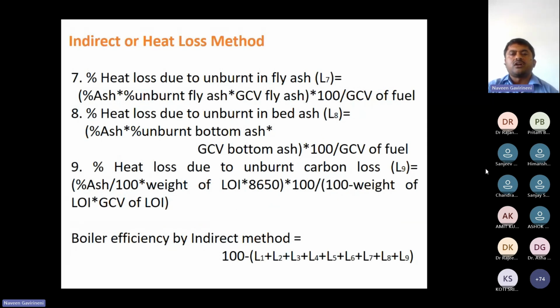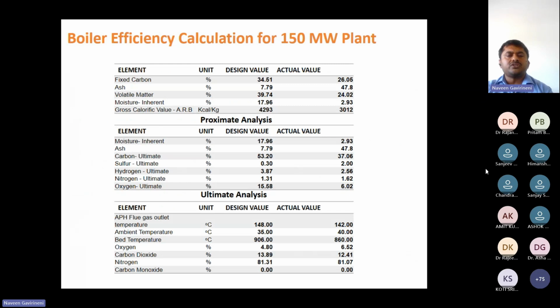The sixth one is the radiation loss and heat loss due to unburnt fly ash, heat loss due to bed ash. So finally, heat loss due to unburnt carbon. Actually, it is the most important point, playing a vital role for the boiler efficiency. After separating all these things, the boiler efficiency will come. So just see this boiler efficiency calculation.